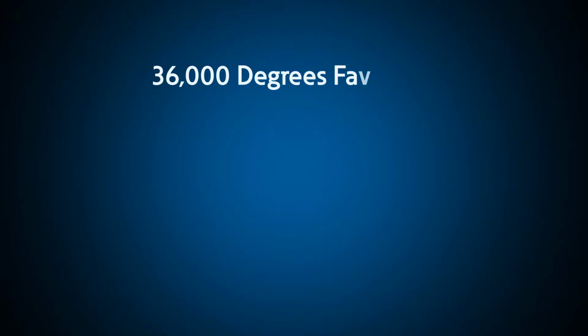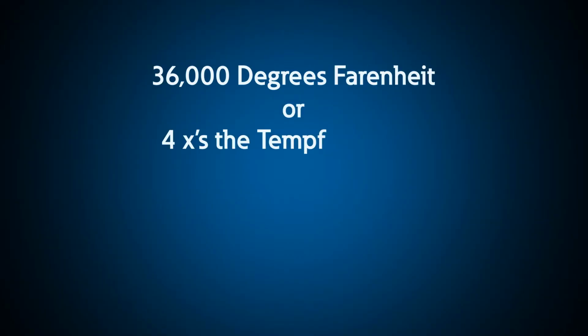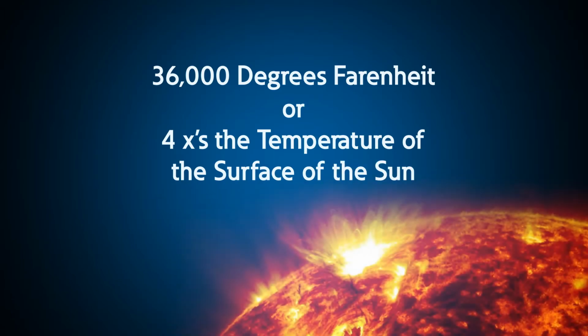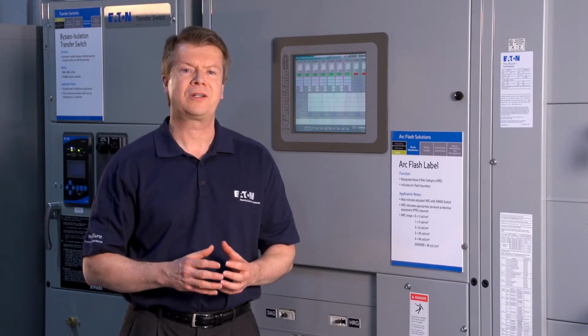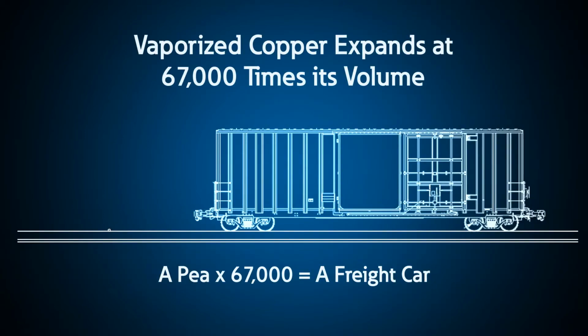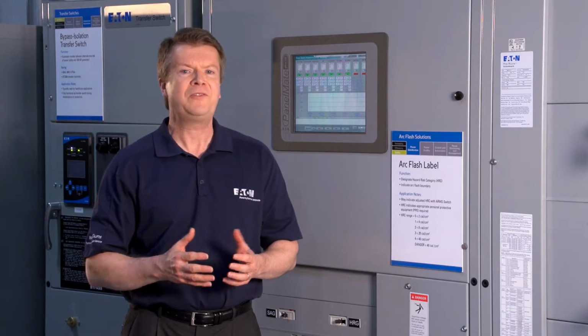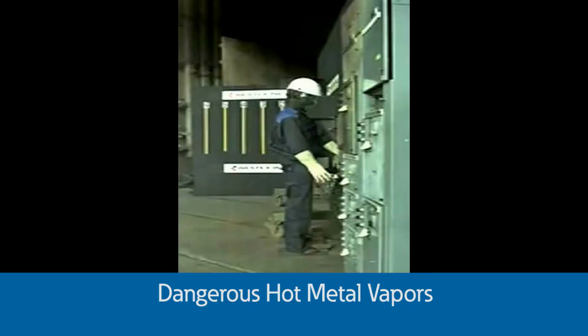An arc flash event can reach temperatures of 36,000 degrees Fahrenheit, or 4 times the temperature of the surface of the sun. During the arc, copper can expand at 67,000 times its volume, very much like an explosion caused by dynamite. And if you're as startled as you would be in the case of an arc flash event, you would quickly inhale and breathe in that vaporized copper.